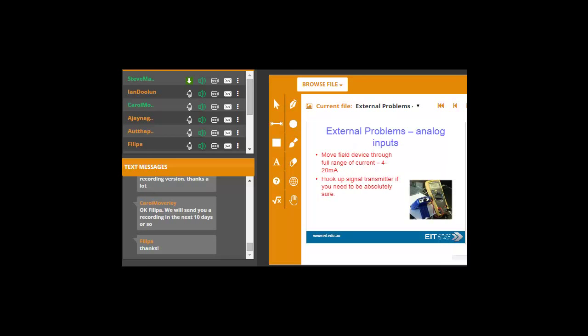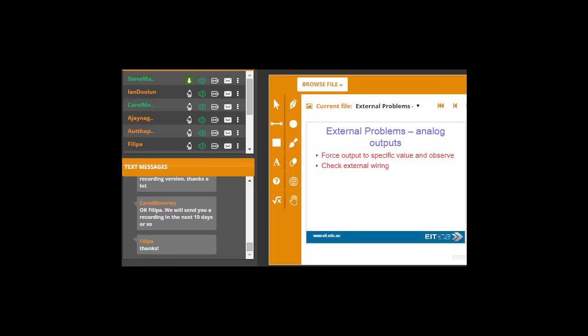Just checking the output on doesn't necessarily mean there's no load that it actually does work in the real world. Any analog inputs, again, challenge here is to move your field device through the full range, 4 to 20 milliamps. 4 milliamps meaning zero, and 20 milliamps meaning 100%. You can hook up a signal transmitter if you need to be absolutely sure. The few subtleties today, of course, is that everything today is HART or digital inputs, as well as a Profibus or Fieldbus or a highway addressable HART input where you've got a digital signal superimposed on an analog input. Analog outputs, obviously, again, force your output to a specific value and observe. Check the external wiring if there's a problem there.